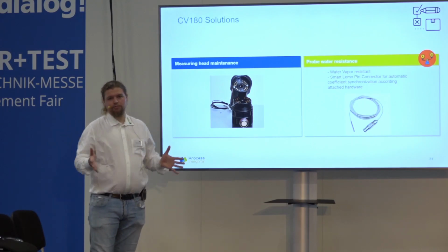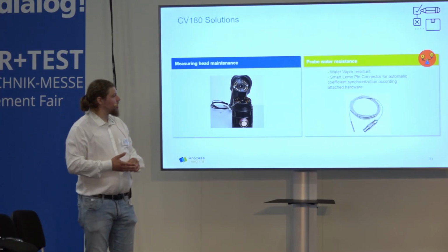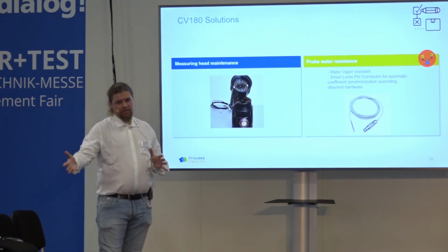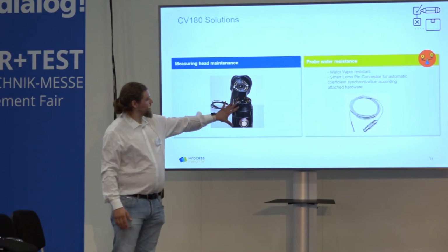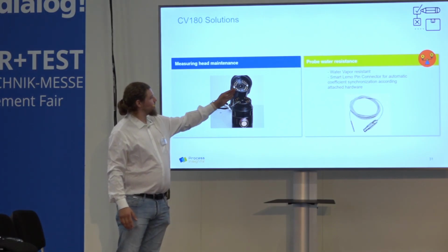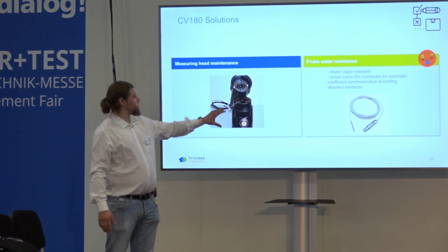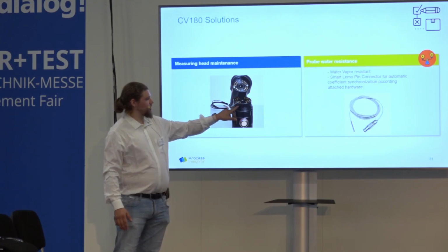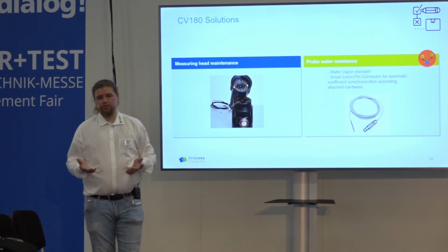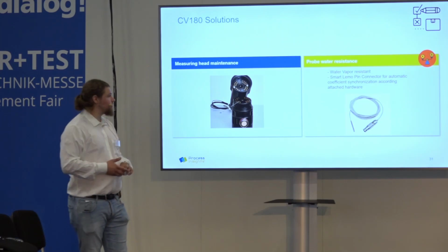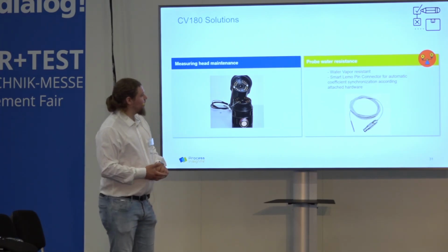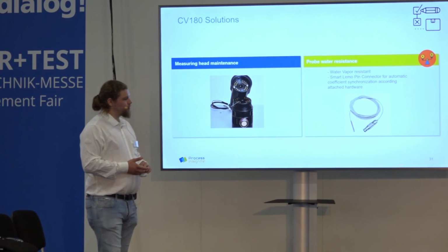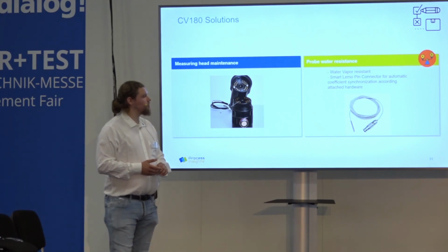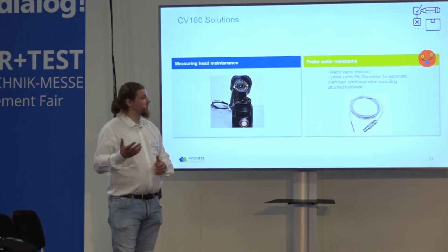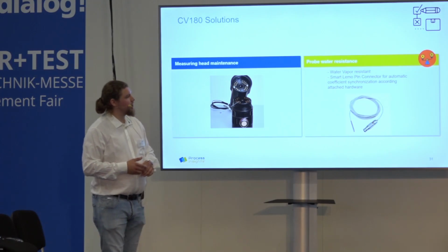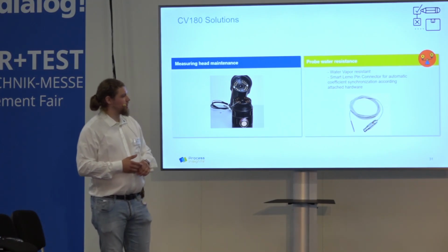You need to do 30 minutes of startup time and 30 minutes of measurement time. Now you can see the measuring head can be dismantled outside of the chamber so that we can do the cleaning without disturbing the conditions of the chamber itself. And on the right you can see the probe which were developed. As we are working with climate chambers with high humidity, they are water vapor resistant, and also there was this connector.